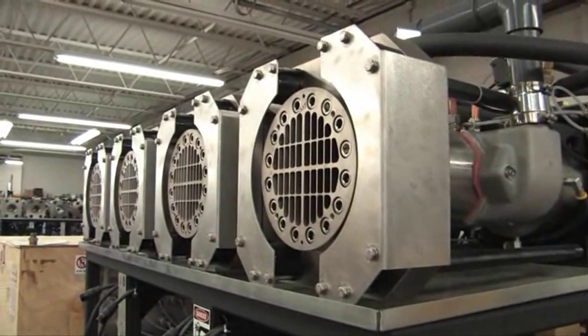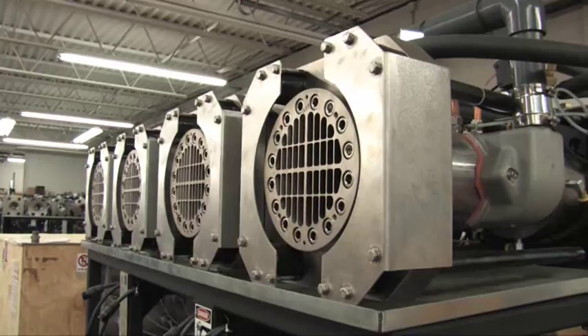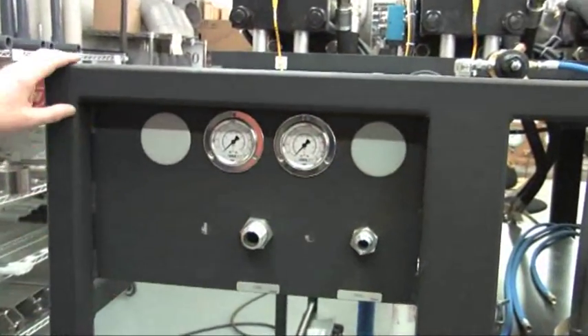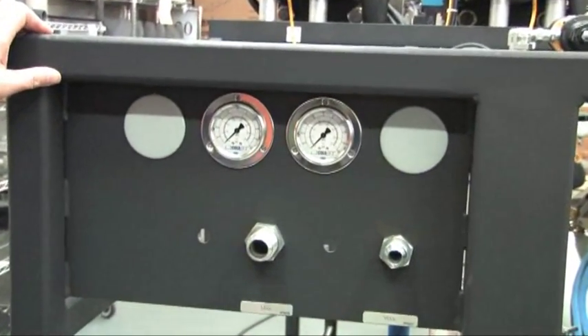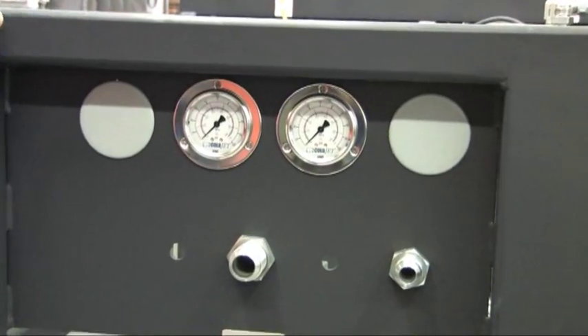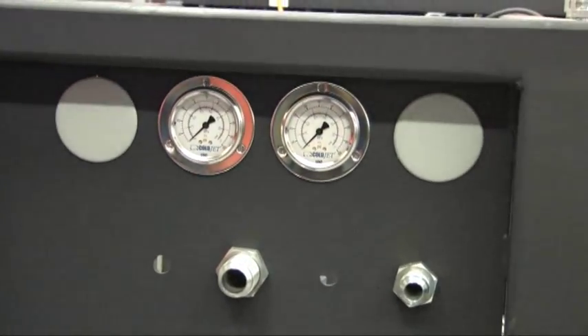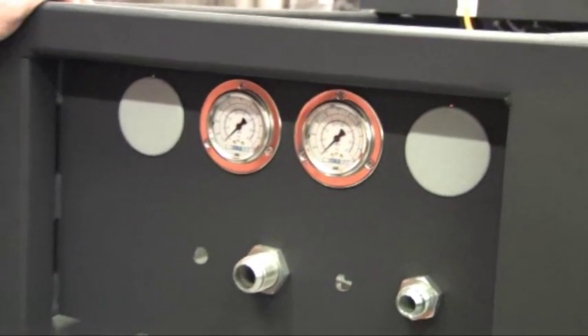We've got the liquid and the vapor hookup. This machine takes a 1-inch liquid line and a 3-quarter-inch vapor line. And basically, we're taking the one liquid line. We're splitting it off into two separate systems there. So it is truly two separate systems.